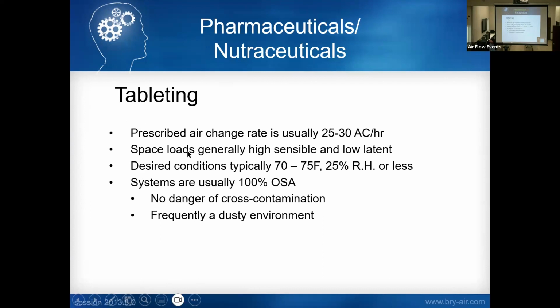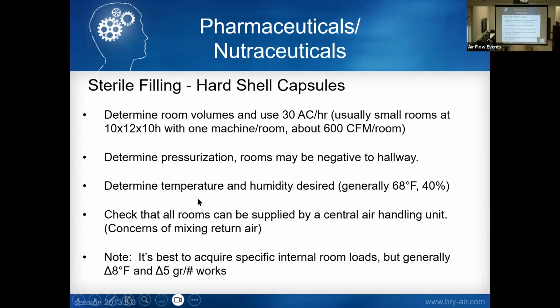Tableting manufacturing process. Typically see these rooms about 25 to 30 air changes per hour. Space generally has a high sensible heat load, low latent. Typically see these about 70 to 75 degree Fahrenheit, 25% RH or less. And typically these are 100% outside air. And it's a dusty environment, so filtration's very critical as well. So you're filtering the return air then before it gets...